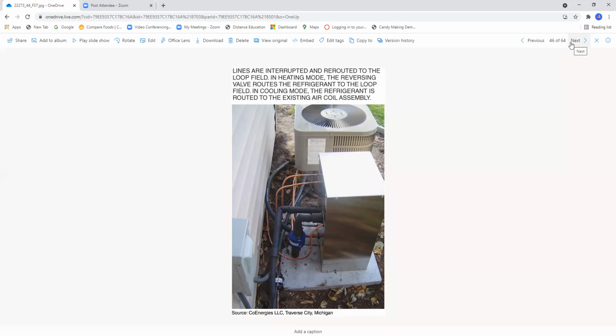What it shows is the insulated supply and return lines routed to the retrofitted air conditioner. The lines are interrupted and rerouted to the loop field in the heating mode. The reversing valve routes the refrigerant to the loop field. In the cooling mode, the refrigerant is routed to the existing air coil assembly. There's a lot of piping here, guys, so if you get a leak, it's going to be a real pain to fix. Hopefully that's a biflow dryer.